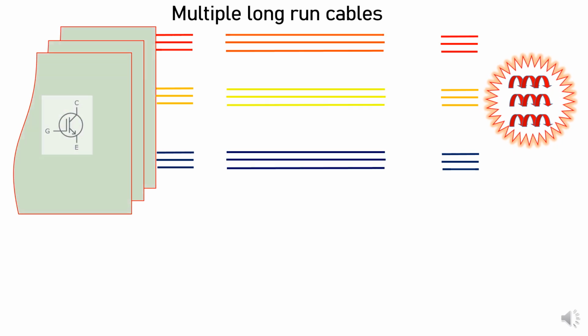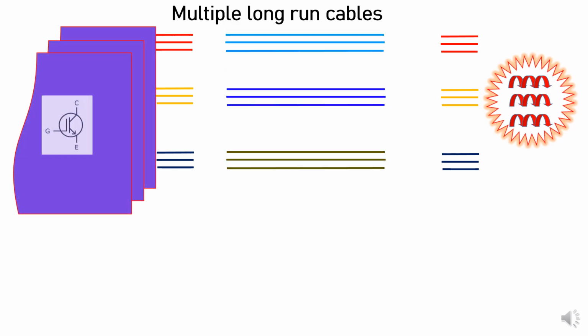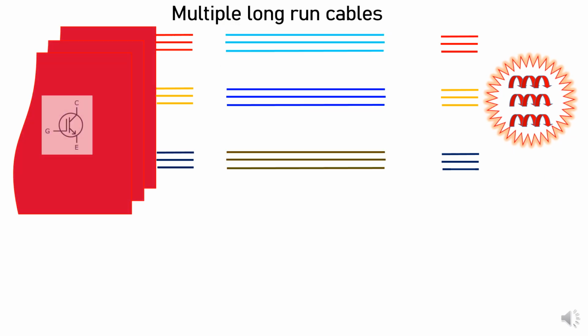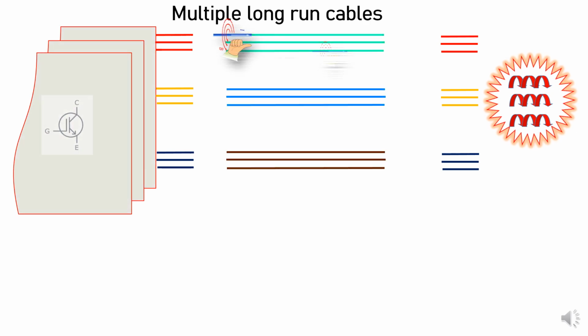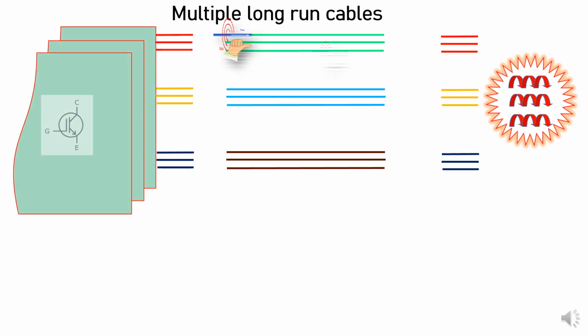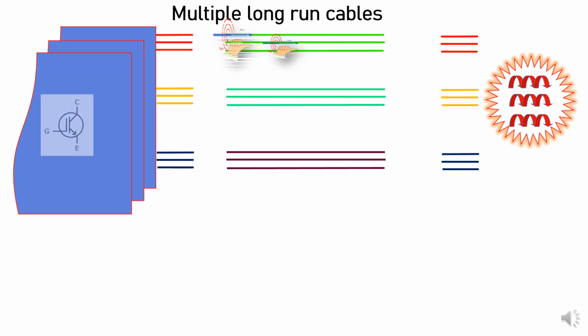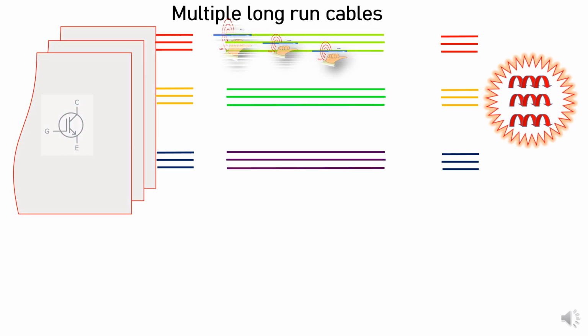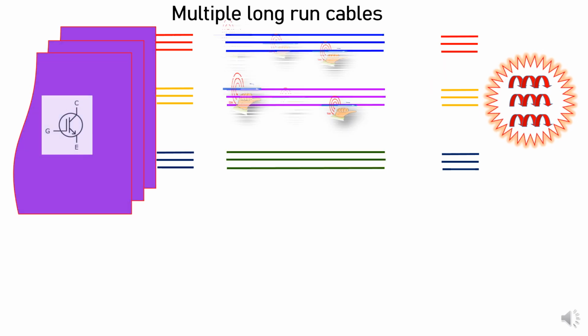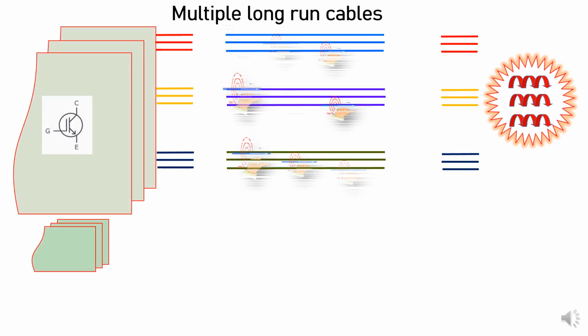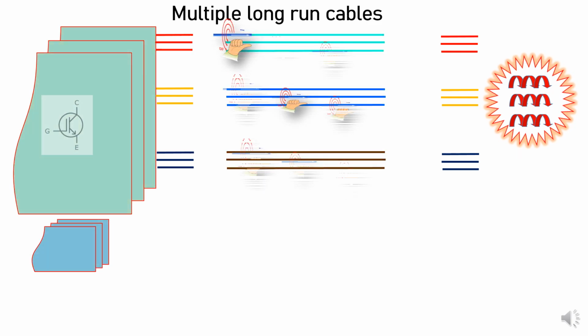Now if you see this type of arrangement, we have multiple long run cables. That is the second area of concern. When we are commissioning the VSD with long run multi-run cables, as per the Fleming right hand rule, it is supposed to generate a magnetic field. When we have connected L1 to L1, L2 to L2 and L3 to L3 in a simple parallel way, all the run cables are supposed to generate a magnetic field. And as per this right hand rule, this field is additive in nature because we have laid the cable in a wrong way.